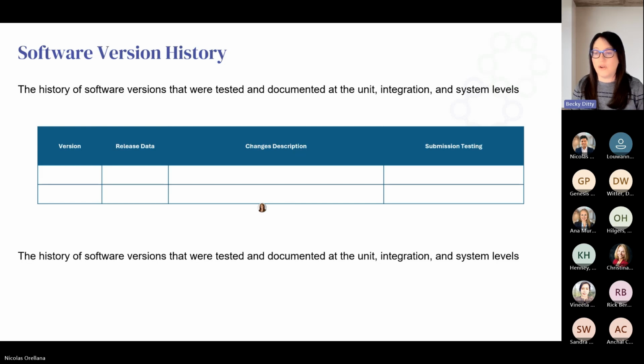And then you do all of your software testing, and you identify that you have some bugs. So you may end up having a third version where you have fixed the bugs that you found in that second version. So that third version is your final finished version. However, you may not have repeated all of your software testing. You may have only done what's called regression testing, where you only tested the parts of the software that changed or could be affected by the change. And so you need to make sure that's explained in the table, and you provide a story after the table that explains why all of the testing that you've done, even if it wasn't on the final finished version, verifies the final finished version, and why some of the earlier testing didn't need to be repeated.